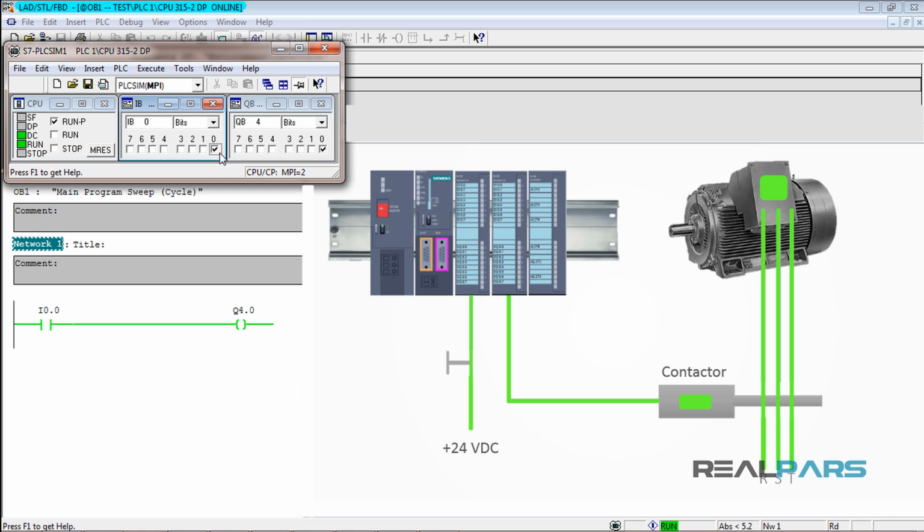So as we discussed earlier, the problem with this latch switch is that it is a momentary switch, and this means that as soon as the operator's hand is removed from the switch, the input is de-energized, resulting in the output being turned off instantly. We want to change the program so that the output is activated continually after just one push of the switch.